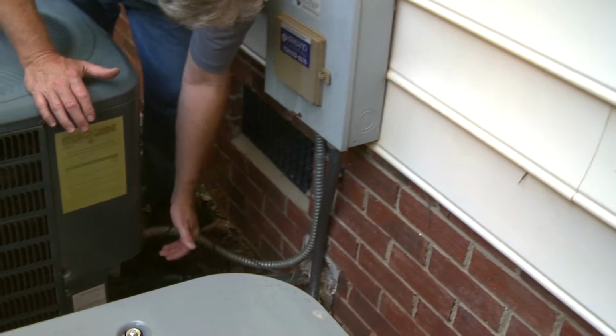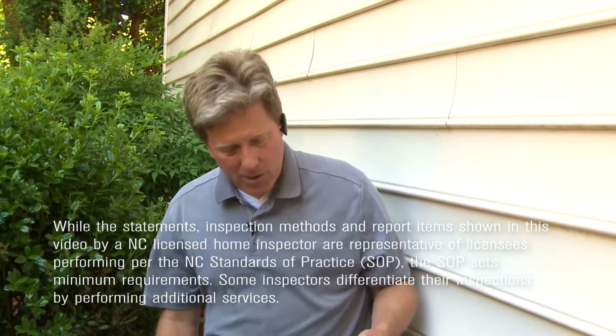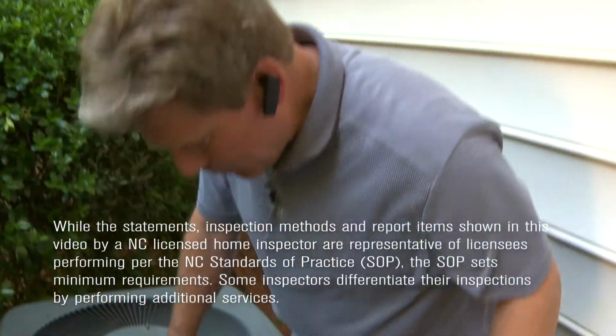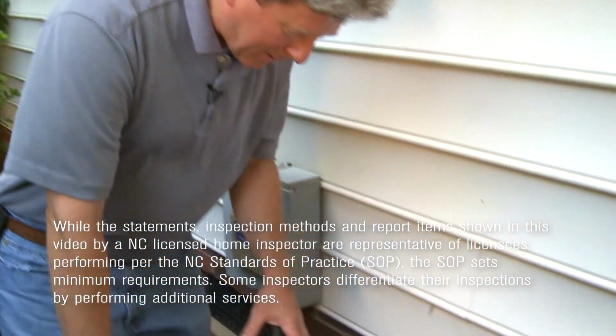I'm going to get down and find the manufacturer's data plate and label, so I can figure out when it was manufactured, the maximum recommended breaker sizes, and other data for both units. Then I'm going to check the platforms.